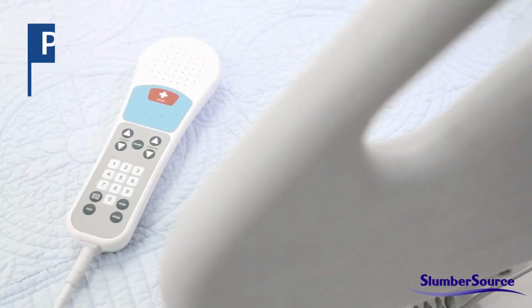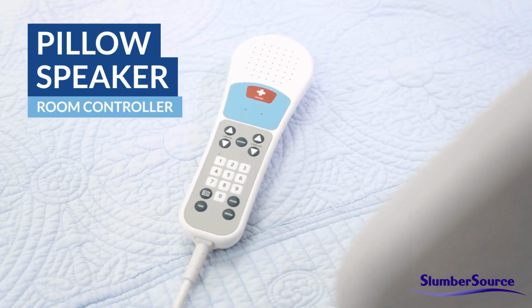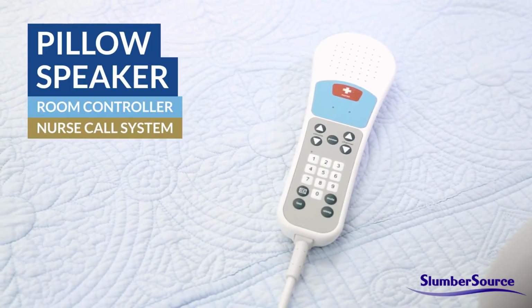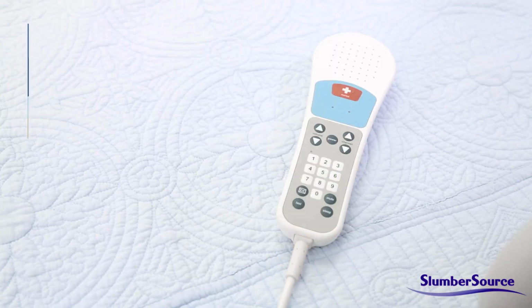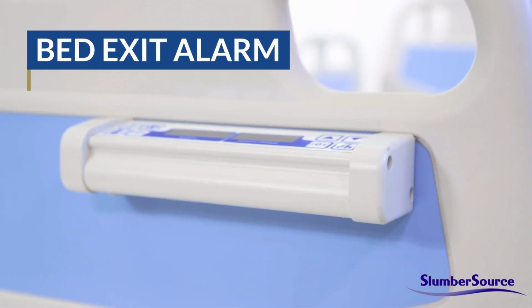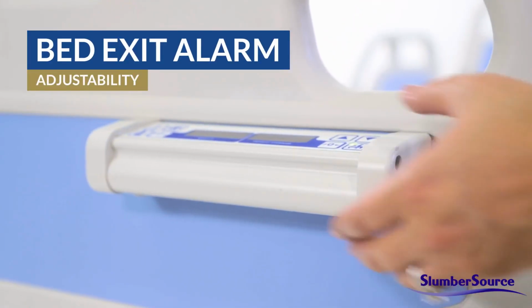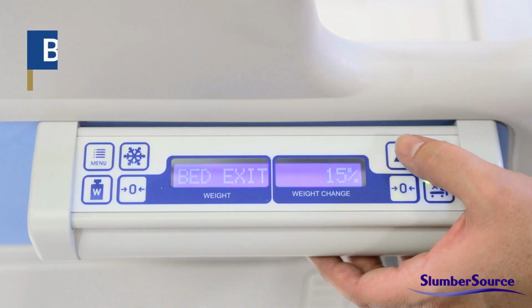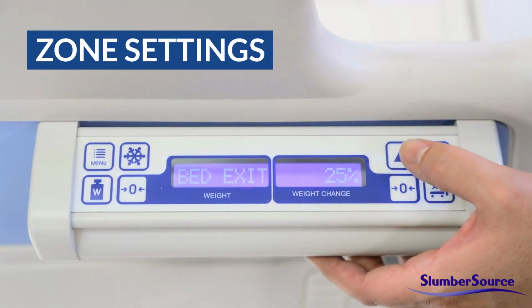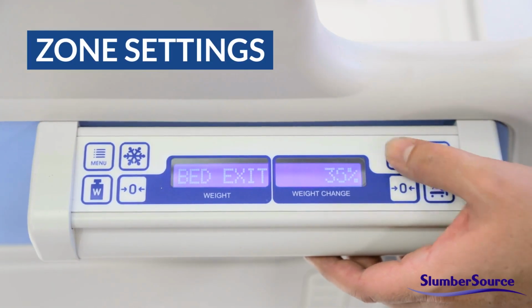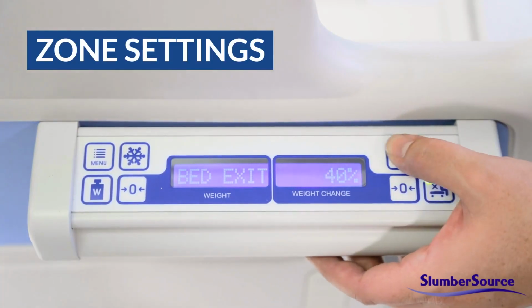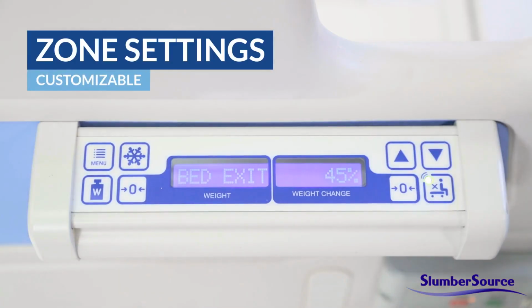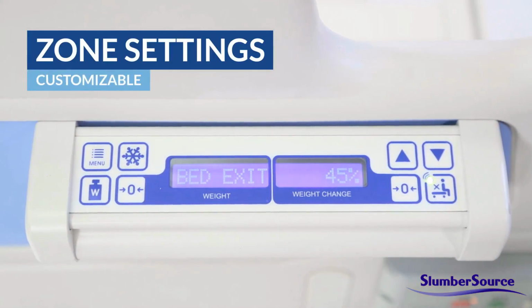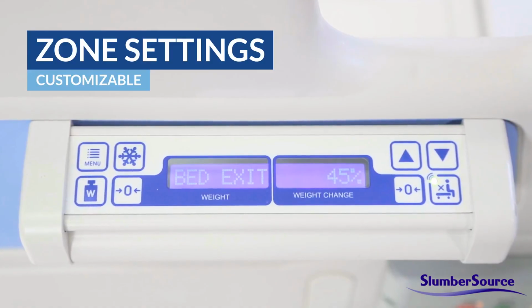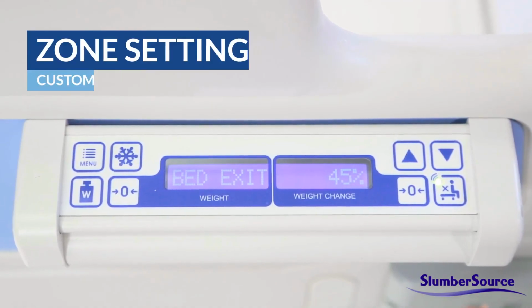For the patient's convenience, a pillow speaker controls entertainment and lighting, and a nurse call button and 2-way monitor assists in communicating with the nursing staff through the integrated nurse call system. The new integrated bed exit alarm has the ability to be adjusted to your patient's needs or requirements. The exit alarm will allow you to set specific zones in 5% gradients, adjusting the level of sensitivity of the alarm system. This will allow you to customize settings for the very active patient, the high fall risk patient, as well as your low risk patients that you feel you still need to keep a watchful eye on.